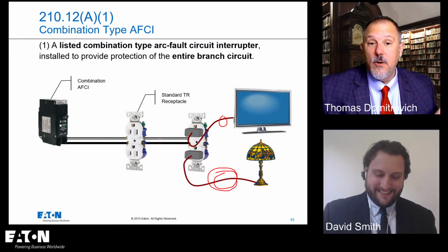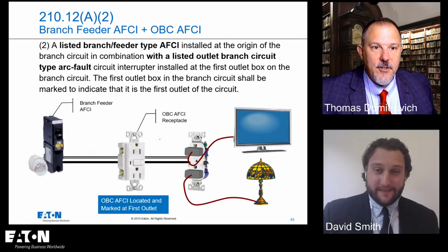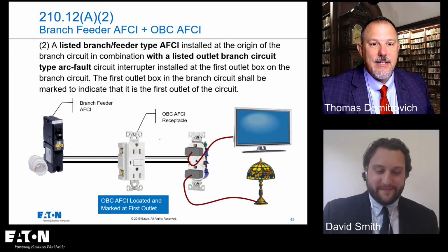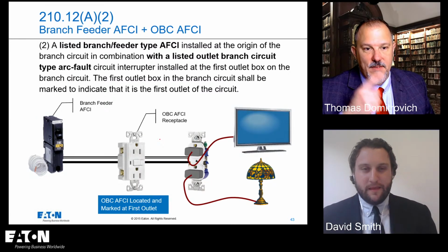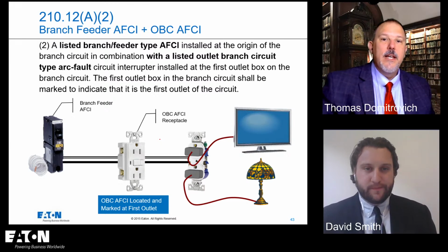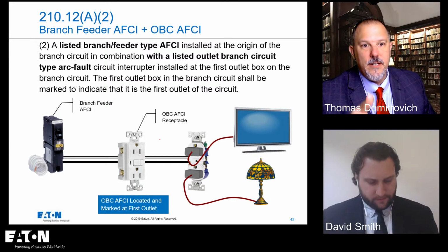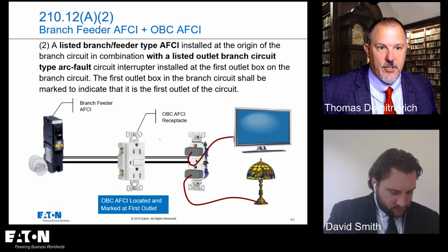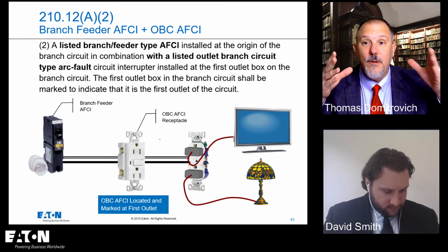Beautiful. Okay, so this is your first option. Now, your second option is a listed branch feeder type AFCI. So this is the branch feeder installed at the origin of a branch circuit in combination with a listed outlet branch circuit type AFCI. Now, there's no distance.